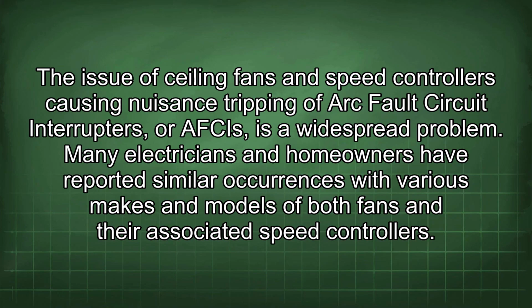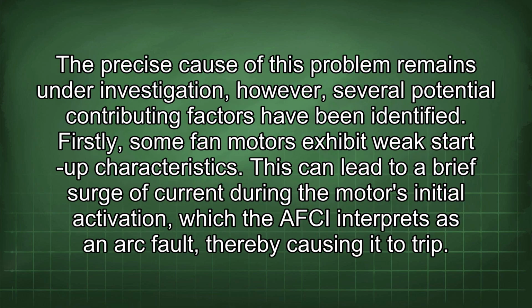The issue of ceiling fans and speed controllers causing nuisance tripping of arc fault circuit interrupters, or AFCIs, is a widespread problem. Many electricians and homeowners have reported similar occurrences with various makes and models of both fans and their associated speed controllers. The precise cause of this problem remains under investigation. However, several potential contributing factors have been identified.